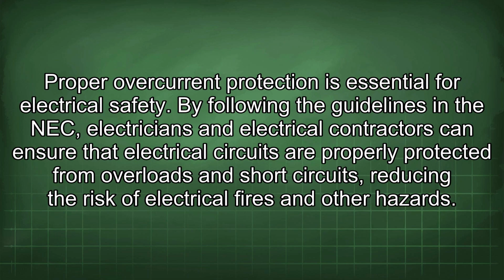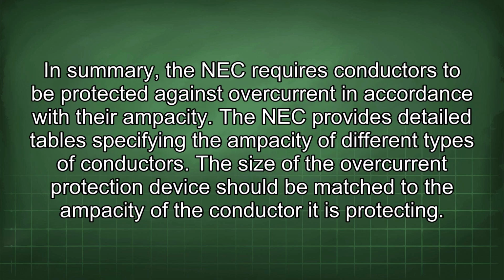Proper overcurrent protection is essential for electrical safety. By following the guidelines in the NEC, electricians and electrical contractors can ensure that electrical circuits are properly protected from overloads and short circuits, reducing the risk of electrical fires and other hazards. In summary, the NEC requires conductors to be protected against overcurrent in accordance with their ampacity. The NEC provides detailed tables specifying the ampacity of different types of conductors. The size of the overcurrent protection device should be matched to the ampacity of the conductor it is protecting.